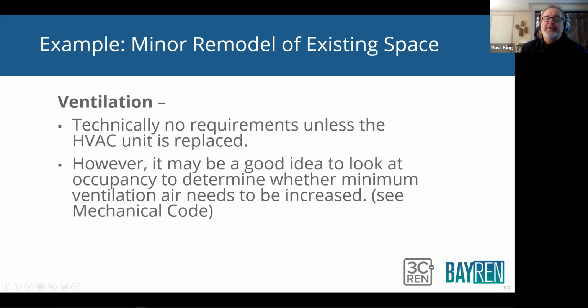Ventilation: technically no requirements unless the HVAC unit is replaced, all right? It may be a good idea to look at occupancy. So what we're talking about again is a TI, and the question is, do we have to address the ventilation? Only if the HVAC unit is being replaced do you have to meet the ventilation requirements of that occupancy, but it's a good idea to check it anyways. And you know, you might have a package unit that does not have an economizer on it, and they're going from a retail space to a hair salon, which has very high ventilation requirements because of all the chemicals that they use. The energy code doesn't say you have to have ventilation, but the mechanical code might, all right? So be aware of related code issues on that side.